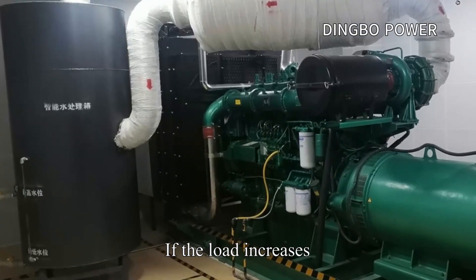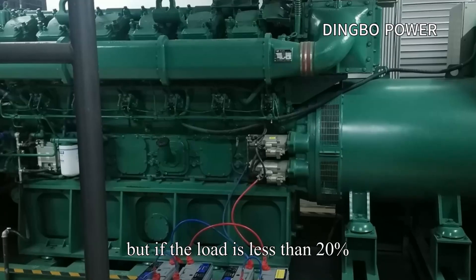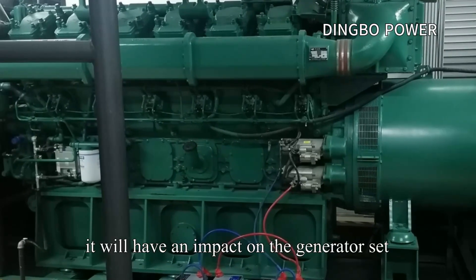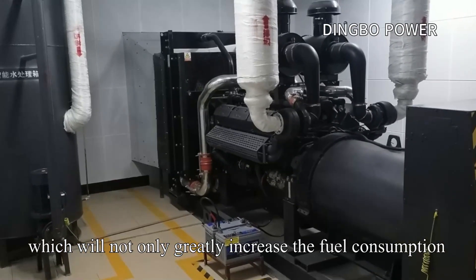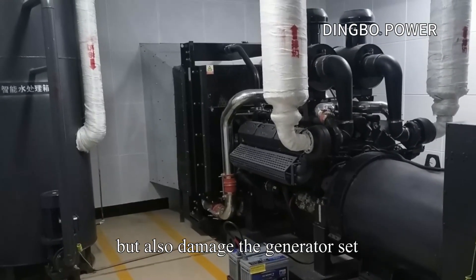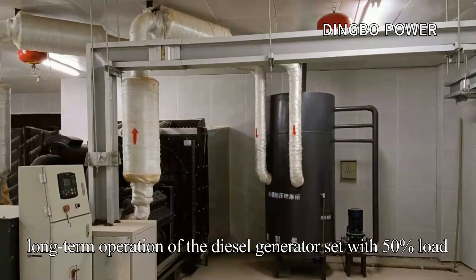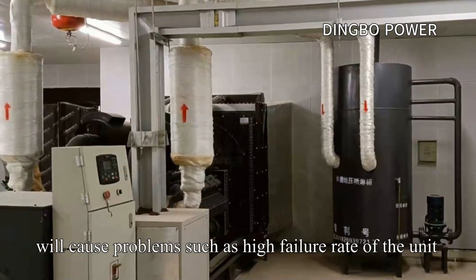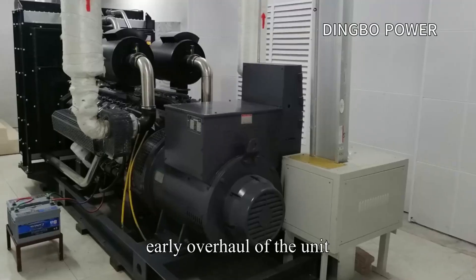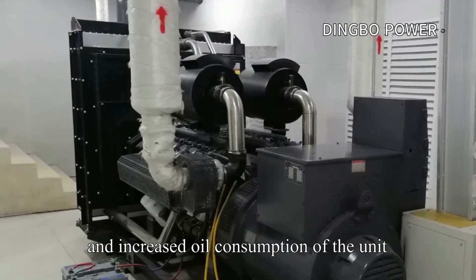If the load increases, the fuel consumption will increase. But if the load is less than 20%, it will have a negative impact on the generator set — not only greatly increasing fuel consumption, but also damaging the unit. In addition, long-term operation at 50% load will cause problems such as a high failure rate, early overhaul requirements, and increased oil consumption of the unit.